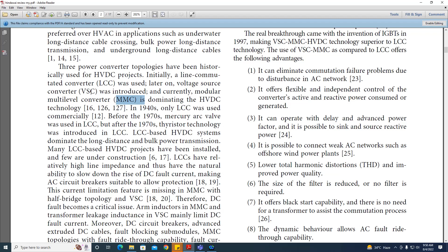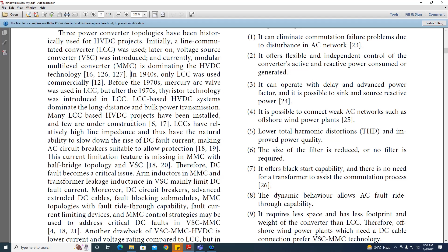In the 1940s, only LCC was used commercially. Before the 1970s, mercury arc valves were used in LCC, but after the 1970s, thyristor technology was introduced in LCC. LCC-based HVDC systems dominate long-distance and bulk power transmission. Many LCC-based HVDC projects have been installed and a few are under construction. The project currently installed in Pakistan from Matiari to Lahore is also an LCC-based project. LCCs have relatively high line impedance and thus have the natural ability to slow down the rise of DC fault current, making AC circuit breakers suitable for protection.